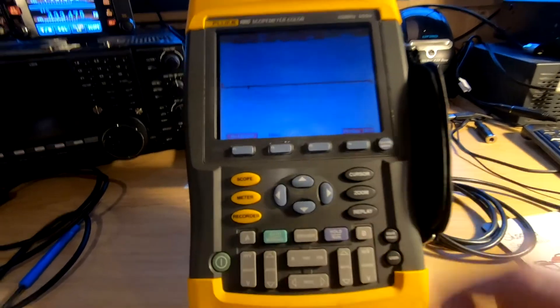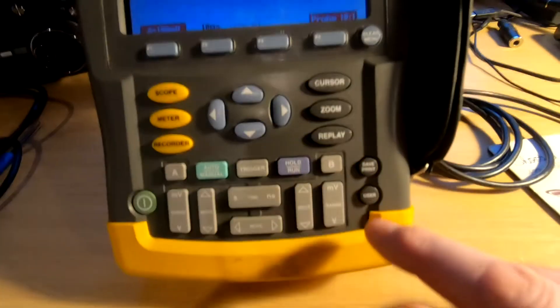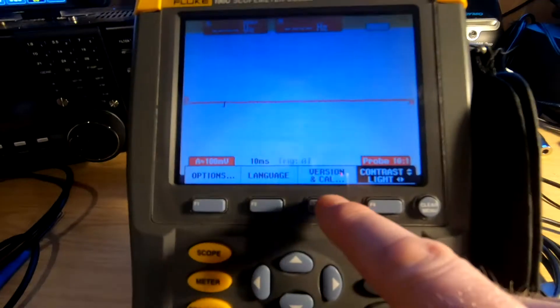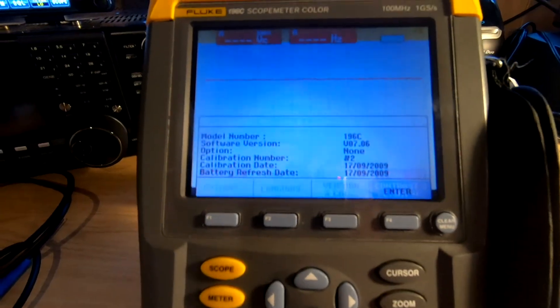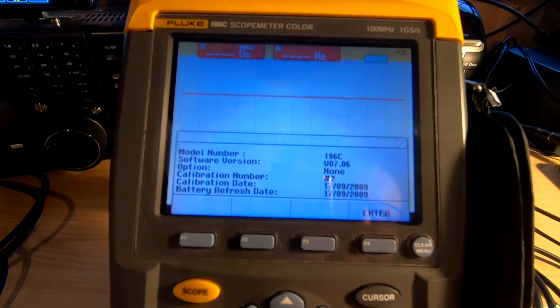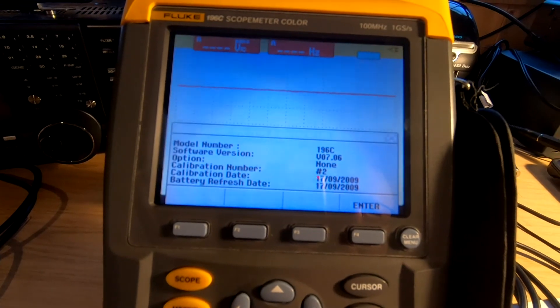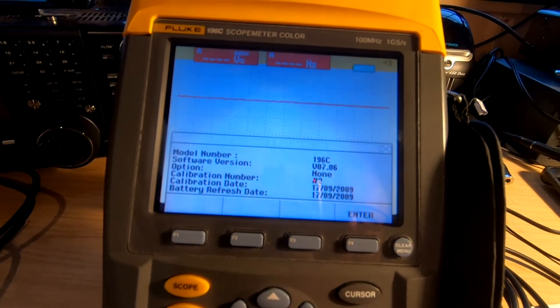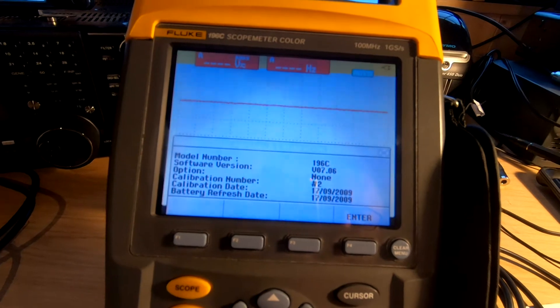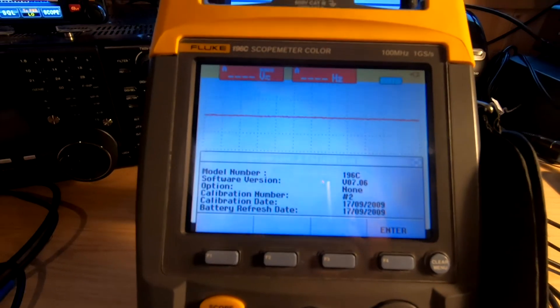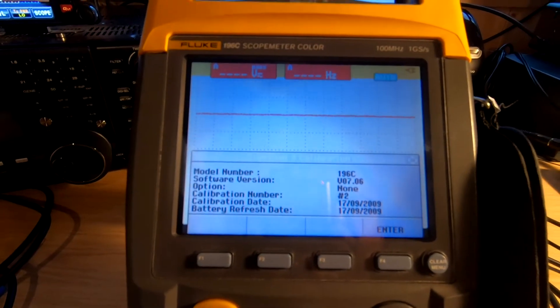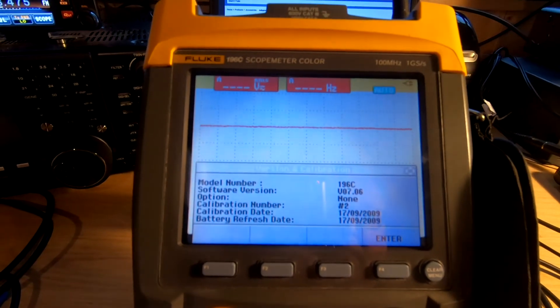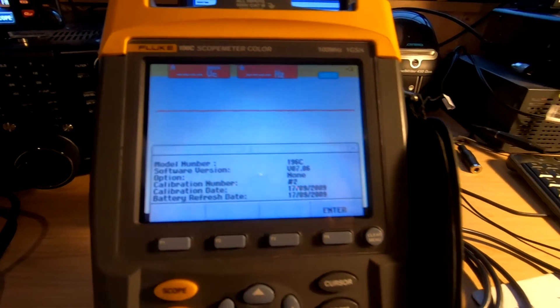Going down to user and pressing user, we've got the version & cal. According to this, it's a 196C running version 7.06. What we're going to do is update that to the latest version of the software, and to do that we're going to need...